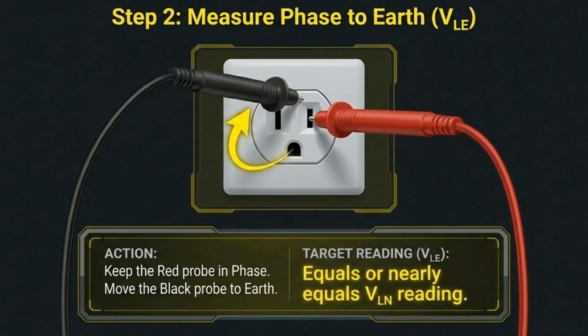Step 2. Measure phase to earth. Keep the red probe in phase and move the black probe to earth. The target reading, VLE, should equal or nearly equal the VLN reading.